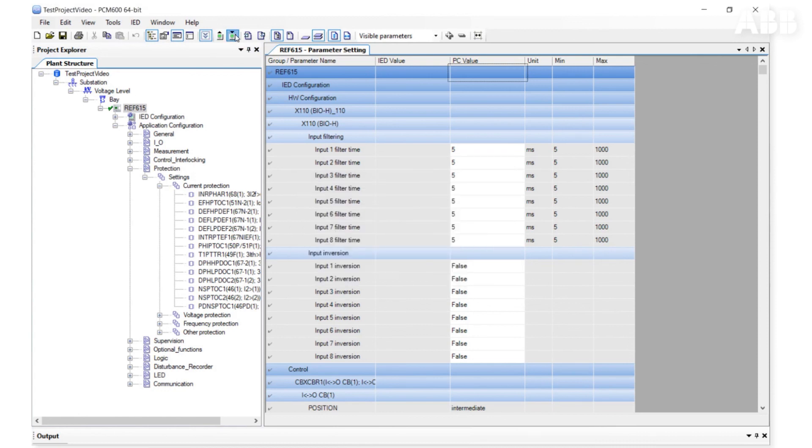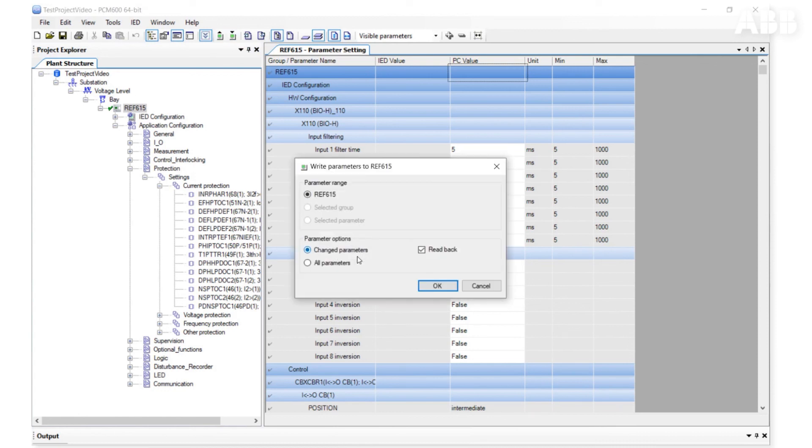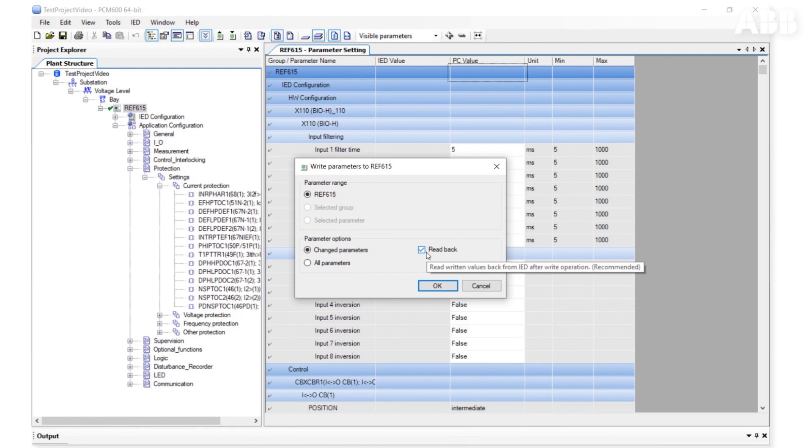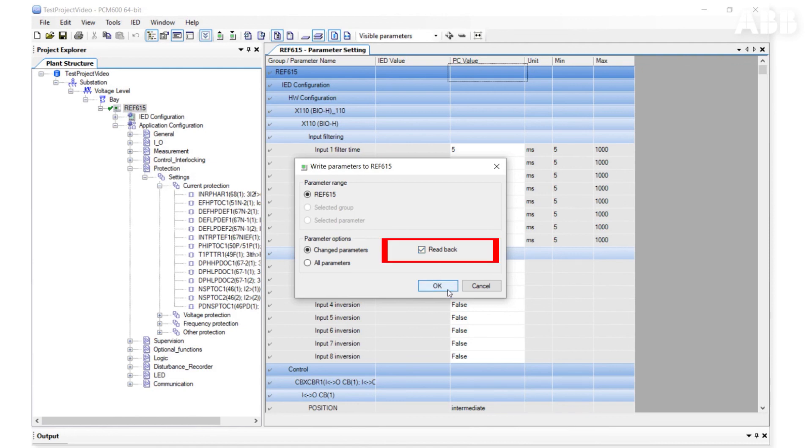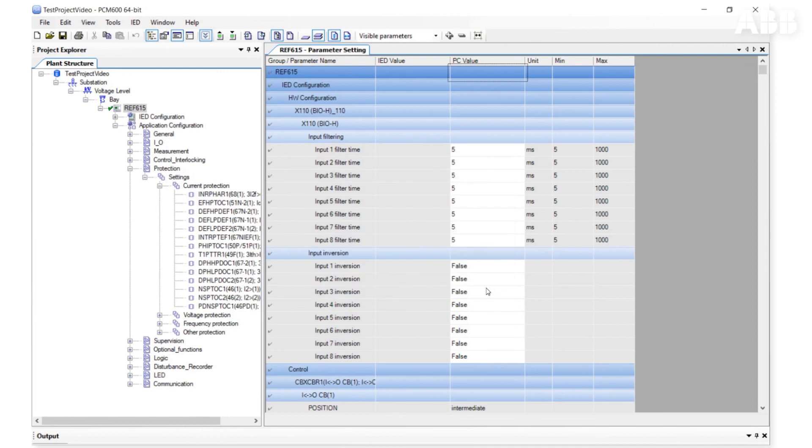Write options are similar to read options. You can write one parameter, a group of parameters or all parameters. When you select Write Parameters to IED, you can decide whether to send only the changed parameters or all parameters for the selected item. If your Read Back option is active, you will read parameters back to the IED value field after the parameters are written to the relay.